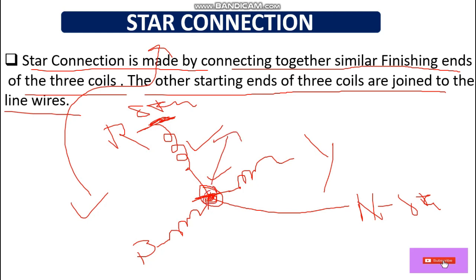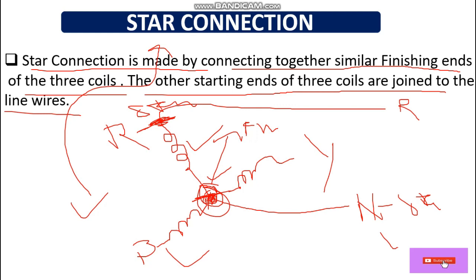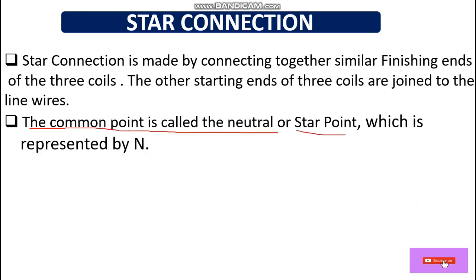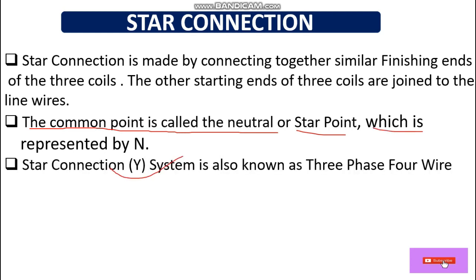The finishing ends of all three coils are joined at one point, and the starting ends of the coils are where we connect the phase supply wires R, Y, B. This connection is called a star connection. The common point is called the neutral or star point, represented by N.